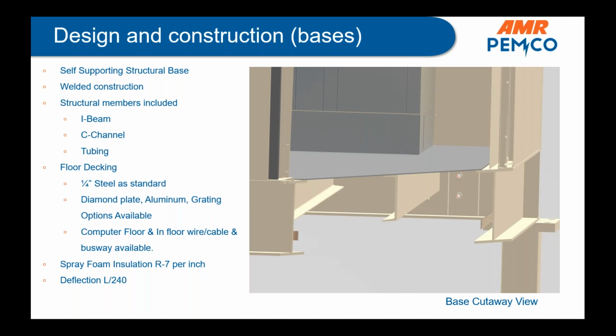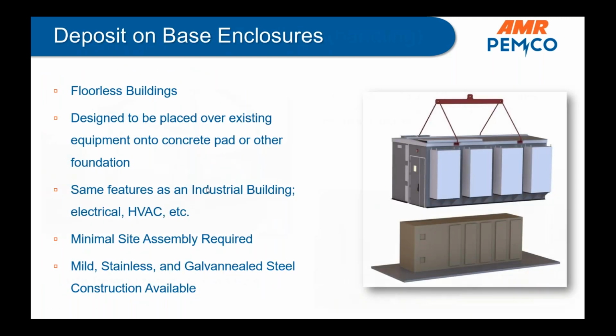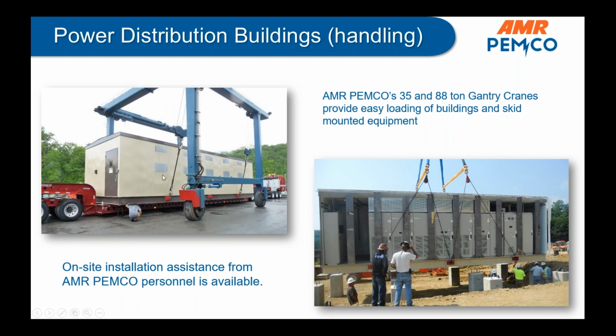Question: do you have the ability to provide buildings with heavy equipment loading? Yes, heavy equipment loading is relative, but this building in the picture had a drive that weighed 43,000 pounds. It also had another bus assembly weighing 8,000 to 10,000 pounds, which we hung off the roof. So yeah, heavy equipment loads, we can handle that. This was a 33,000 horsepower drive, and it weighed somewhere in the neighborhood of 50,000 pounds. That's just one example.